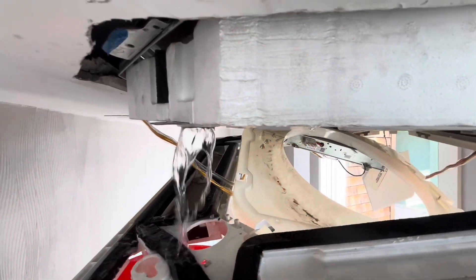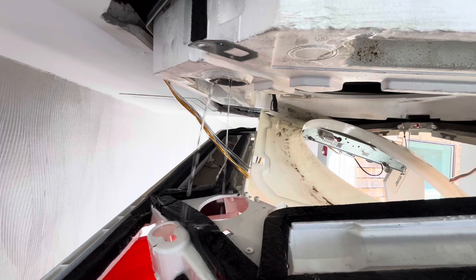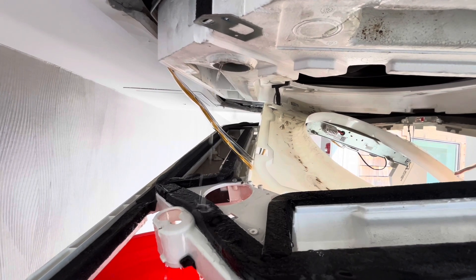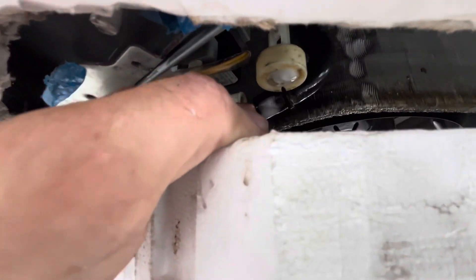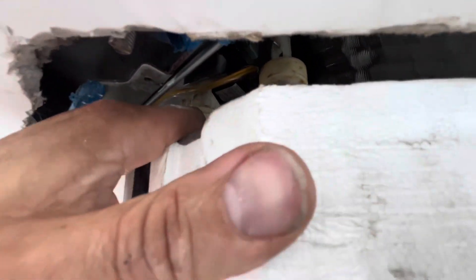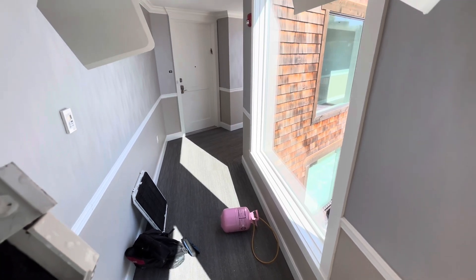I'm going to move this black right here — and there's nothing in here right now. That'll do it every time. Look at this — you want to know why the discharge line's off? That's crazy. It doesn't even look like it was just sitting in water. That's why. Let me throw this discharge back on. I was going to flush it with a little 410 gas vapor, but I'm going to get this on and then re-zip tie it so it stays on and I think they're going to be good to go. Here's the little float switch.